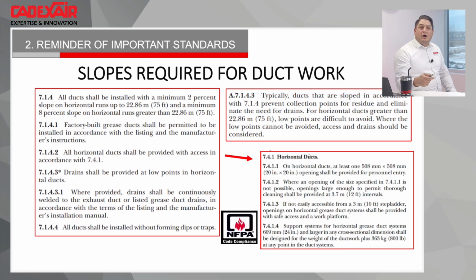And also the drain needs to be fully welded. Also, I think I had an animated discussion maybe 6 months ago about that part in the NFPA 96. It's called the horizontal duct. They say that all horizontal ducts shall be provided with access in accordance with 7.4.1. What does it mean? Technically, when you have horizontal ductwork, you're supposed to have an access door every 12 feet and at every change of direction, okay?